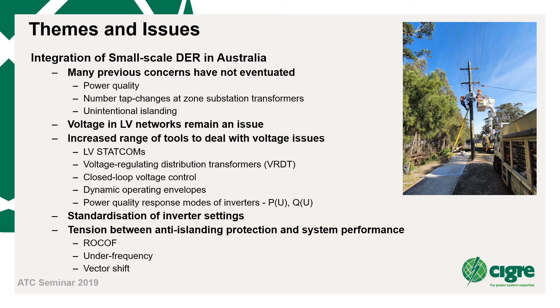As problems at the distribution level with the integration of PV are being addressed, the sheer quantity of DER installed is starting to create issues at higher levels in the network. This can be seen in differing requirements for rate of change of frequency, under frequency, and vector shift protections. From an anti-islanding perspective, the desire is to have tight settings for these protections to enable fast tripping. However, from a system control perspective, it is preferable to have looser settings so that the DER can stay connected and continue to generate during a system disturbance. It's also becoming very apparent that some sort of control will be required over rooftop PV as the proportion of total load it supplies steadily increases in the system.